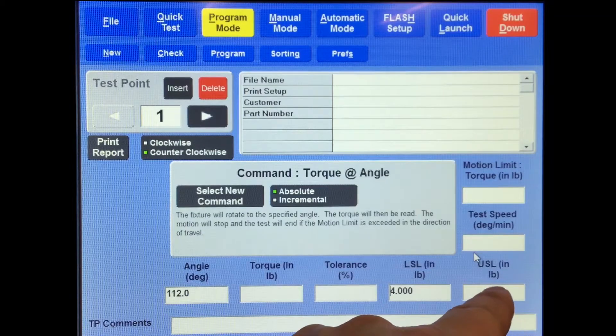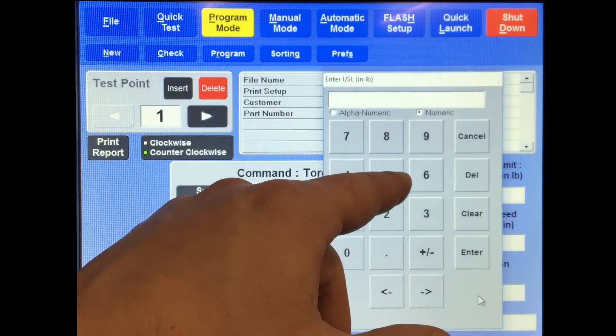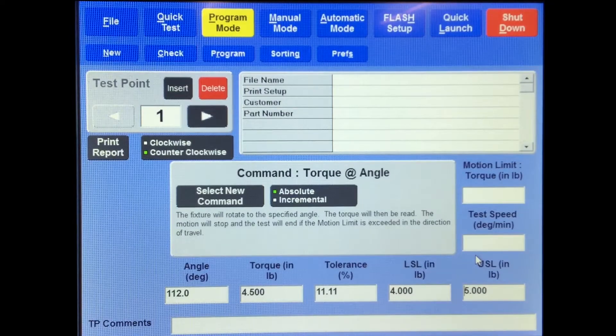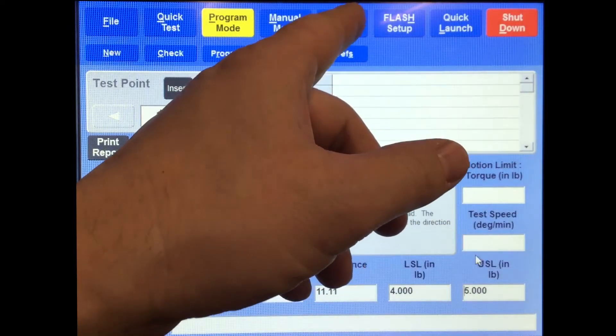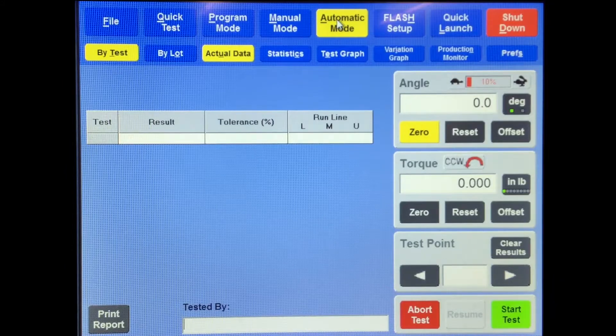On the low side, it can be as good or as bad as 4 inch pounds, and on the high side it can be as good or as bad as 5 inch pounds. So that gives me what I need. Then we're going to go to automatic mode and we're going to try it out.